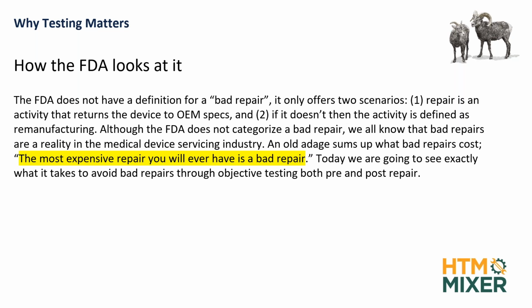is, well, if it's not the right thing to do, you'll see what I mean. If the physician comes up and says, listen, I'm doing a little experiment, I need you to change this widget here and put this one in and wire it in, and you do all that, the FDA is not going to storm the Bastille and come get you for doing that. But before you can ever send that machine out of the hospital again, back into commercial use, like a trade-in, you have to unbundle that, because it would be considered an adulterated product. So you are not in that category that we're going to be talking about today.